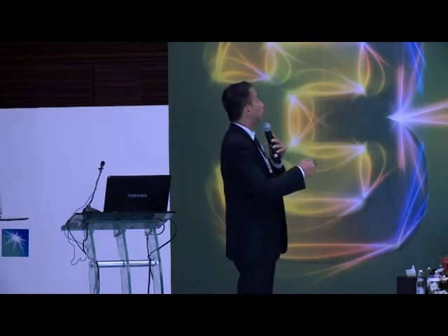And if you ask me, is there anything wrong with this picture? I'm like, no. If you look at it, you see the motor curve. If you push start on the motor, it draws a lot of current. After a few seconds, it accelerates the speed, and then it will draw normal current.